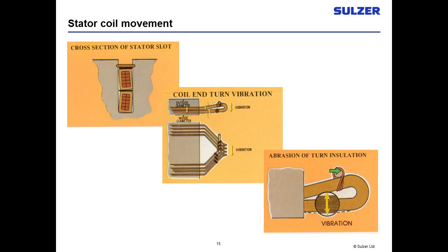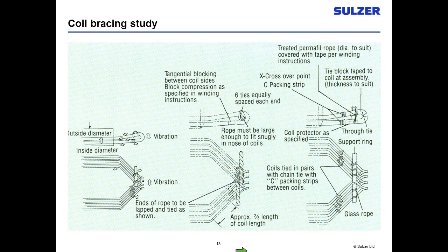We have to keep an eye on this bracing. When motors come into our shop, we look for indications of vibration — to see if the ties are coming loose, the tangential blocking is coming loose, surge ropes are coming loose. If you've changed your operation — say your equipment is taking longer to accelerate, or your voltage or ambient conditions have changed — we need to go in and change the blocking to secure these windings. If you send a motor in and it's failed early, tell us, and we'll find out if your operation has changed or if the coil is loosening due to age.